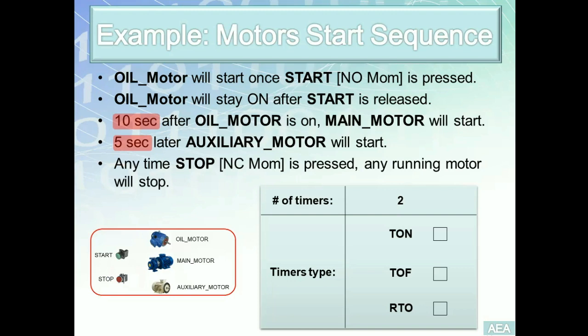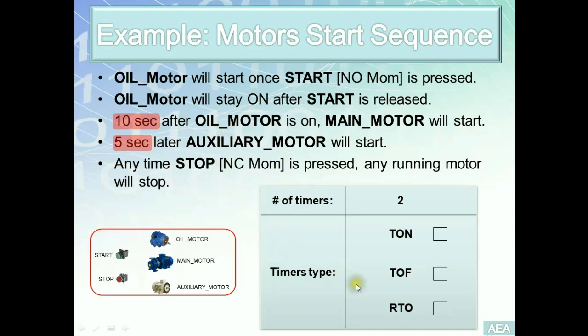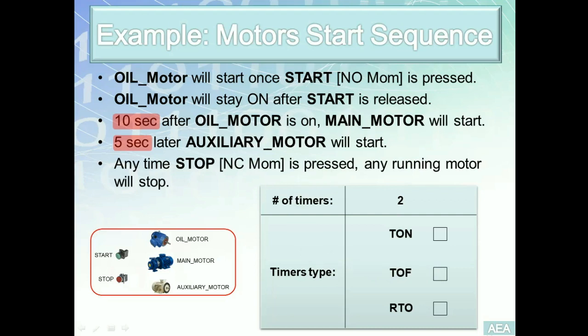However, remember this, it's always, depending on the requirement that you are building and the program that you want to achieve, it would be easier to go with one of these timers, depending on the requirements. Now, as for this example, since we do not see any requirement that talks about retaining or maintaining the value of the accumulator after we hit the stop, it means the retentive timer should not be used over here. Similarly, there is no other requirement that shows us if we want an output to remain on after the stop is pressed. That's why it's easier to build the solution using timer on delay, the non-retentive timer.